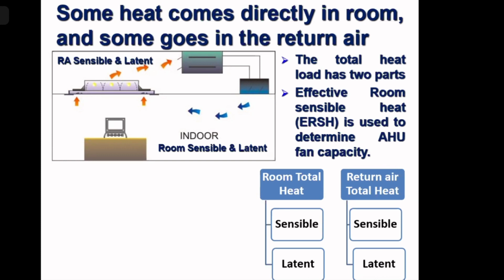So that will also form one part of the cooling requirement of the cooling coil. And then the return air, both sensible and latent heat, which we are adding in the return air part, that also has to be cooled in the cooling coil. So cooling coil has to do everything. So cooling coil sizing has to be done on the basis of all the heat.